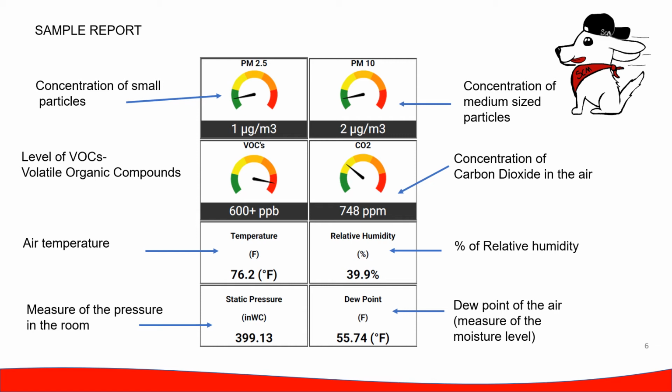Then the relative humidity level, so how humid does it feel in your home? Typically the target range for this is around 50%. In this example it's 40%, which is on the low end of the scale. Around 40% is when things like wood start to dry out. On the other end of the scale, getting into 60 plus is a concern level, where it will feel quite hot and humid, like being in parts of Florida or out on a very hot, muggy day.